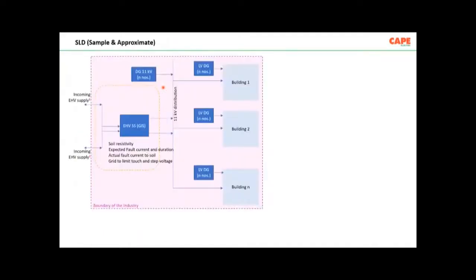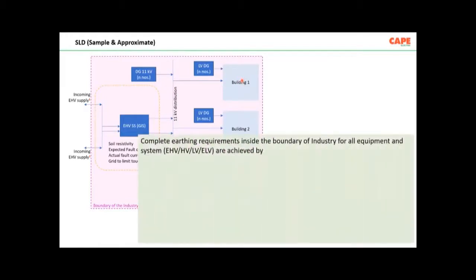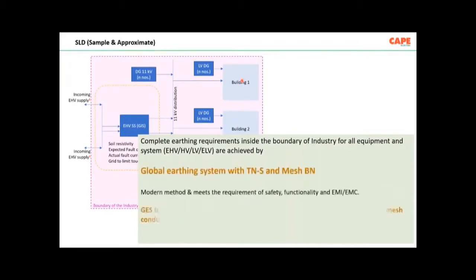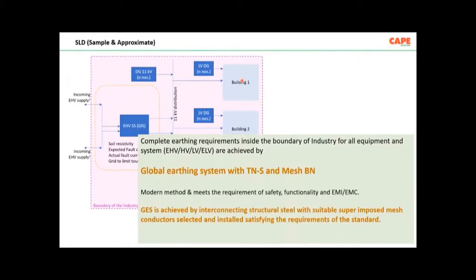What it means is, imagine you have a large building, for example a data center, where there is an EHV supply, you have 11 kV distribution, you have buildings with 11 kV supply and a lot of transformers, sometimes transformers in each floor of the building. For that particular application, the global earthing system is an earthing system which is achieved by interconnecting different earthing systems together. This is the most modern method of achieving safety in a large industrial installation or in buildings where you have your own transformer.